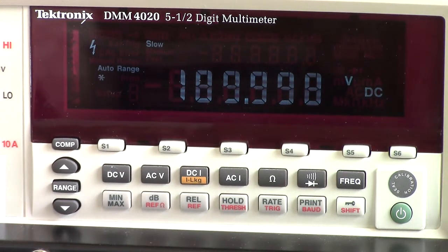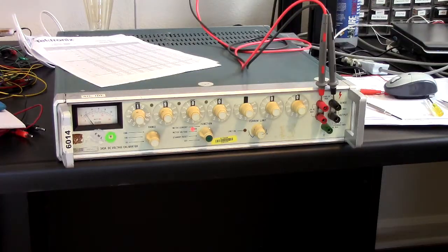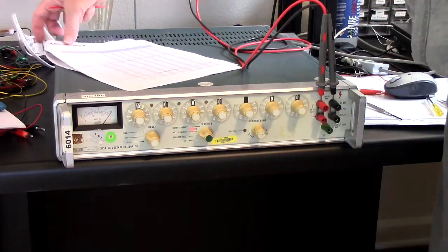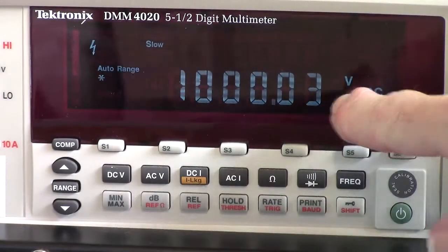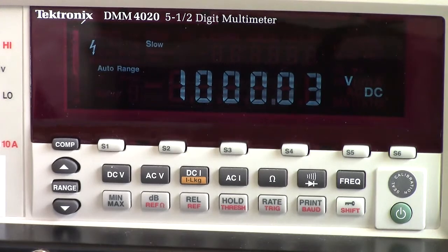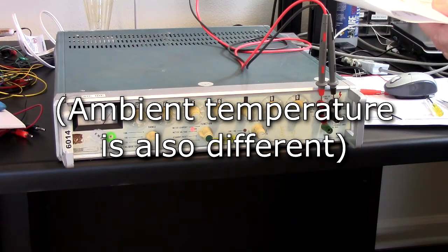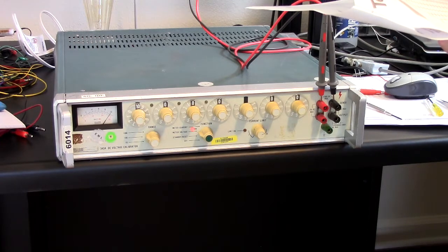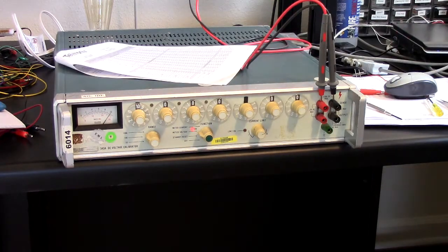When it was calibrated, it read 190.001 on their equipment, but anything between 189.966 and 190.034 is considered in spec for this meter, so this one is showing pretty much in spec. They measured at 1,000. I've got 1,000.03 without everything warming up. He got 1,000.01, but 998.82 to 1,000.18 is in spec. So yeah, this is actually looking a little better than a parts unit.